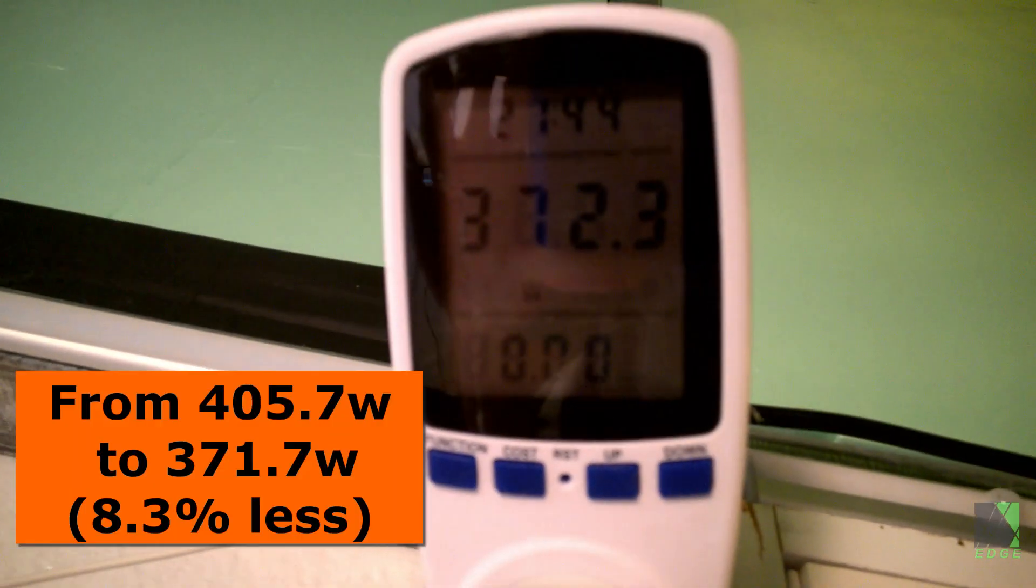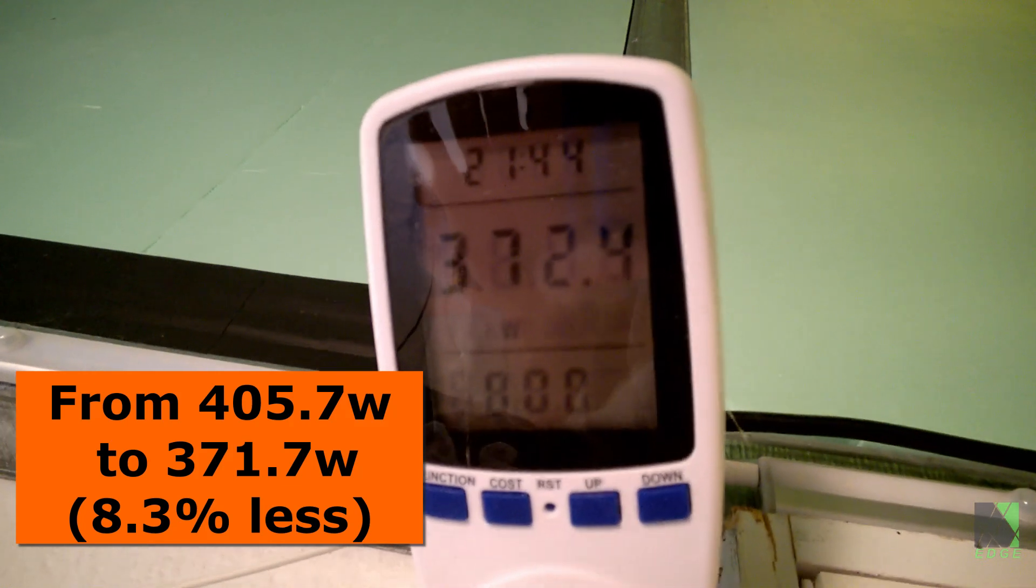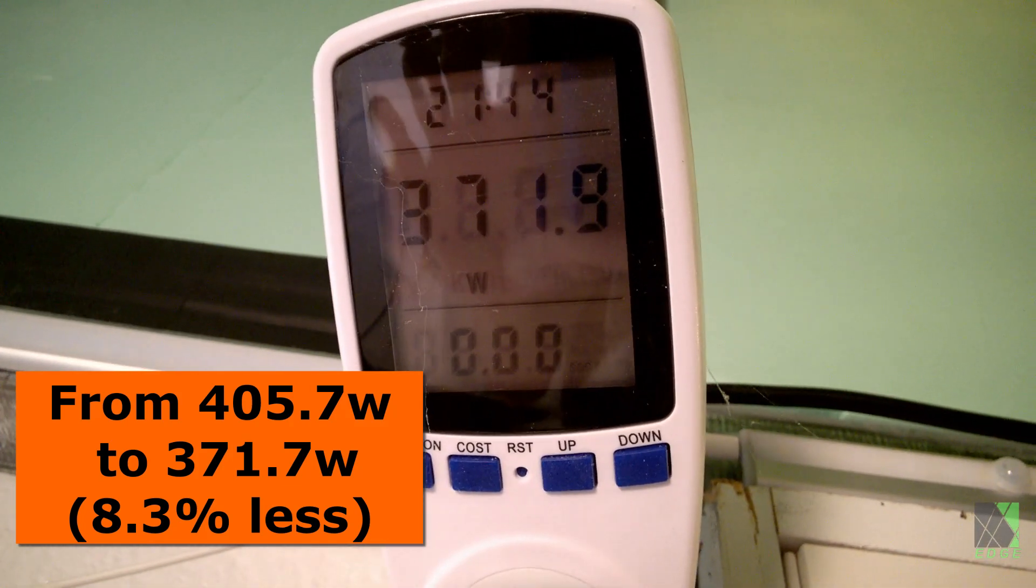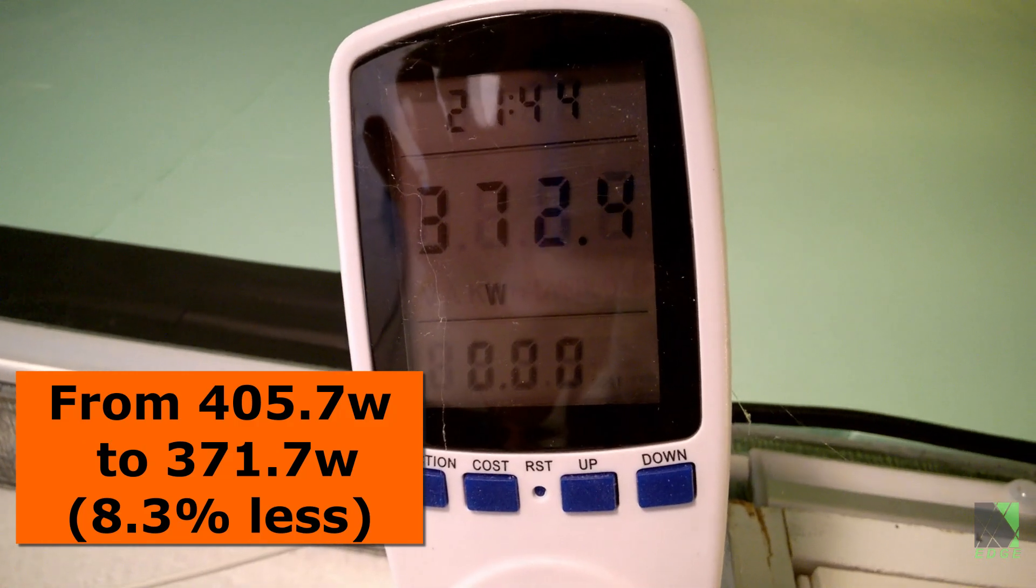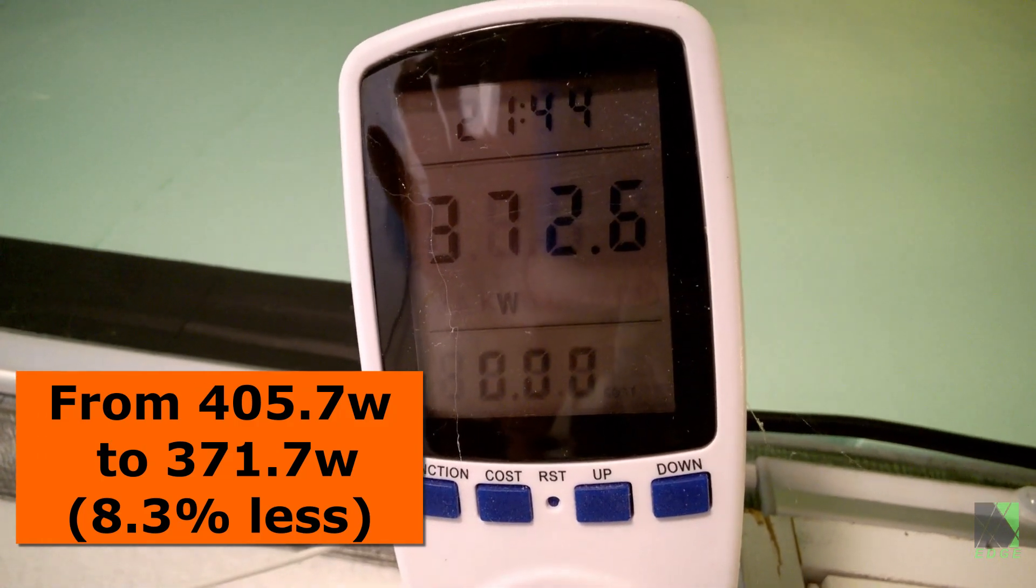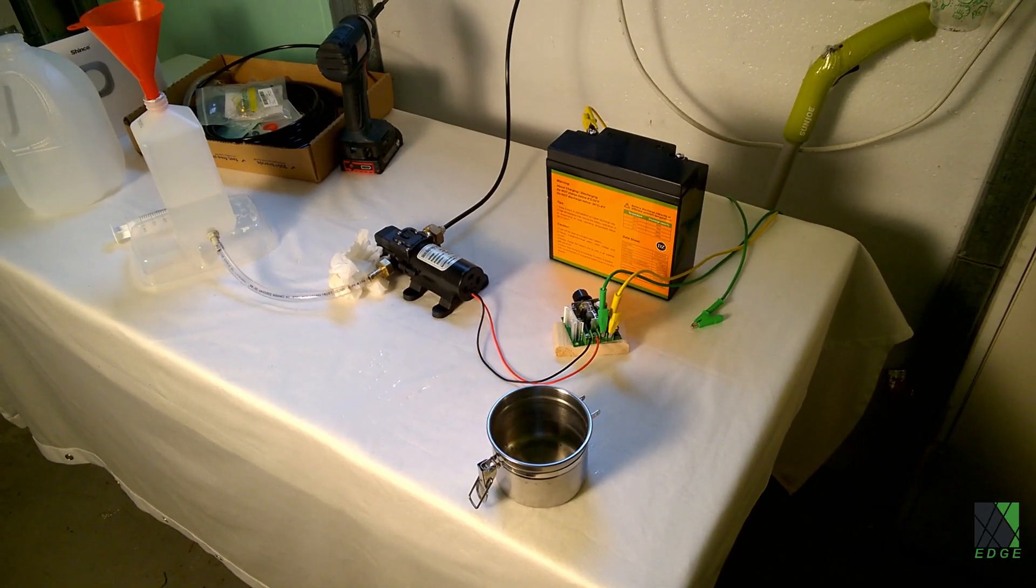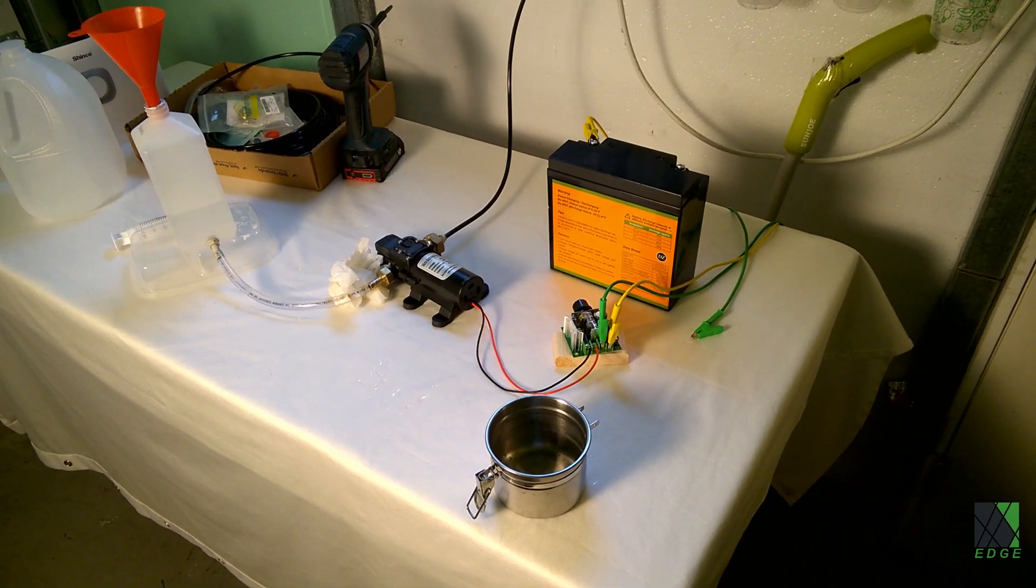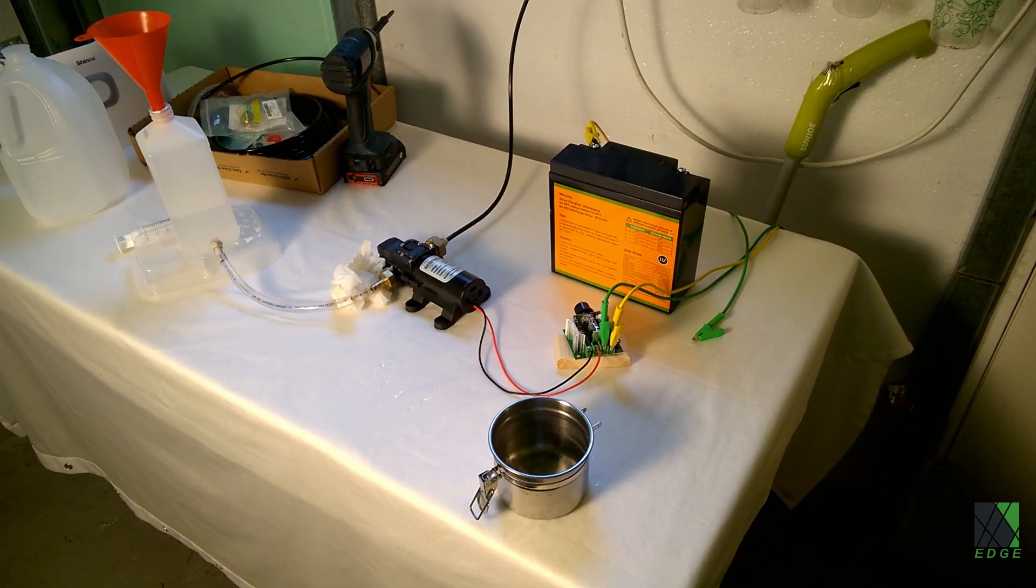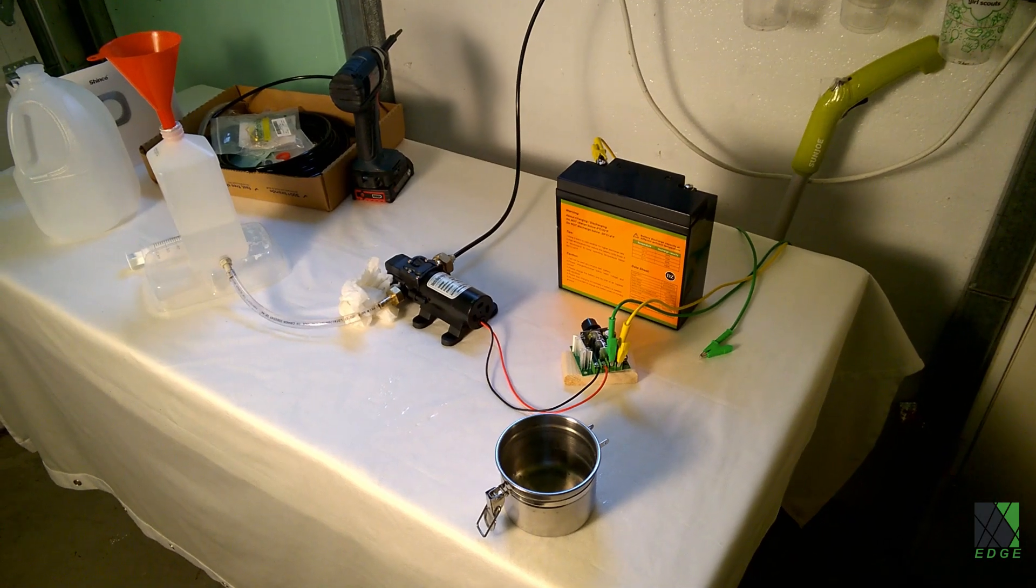After the misting starts, look what happens to the wattage readout. In my experience, this sort of technique does not reduce the amount of cool air you get out of the air conditioner, it just reduces the wattage that it operates at.